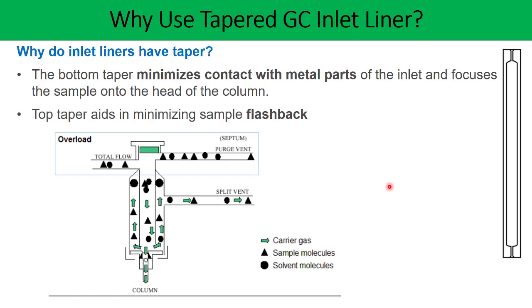The second important reason to consider using the taper liner is that the top taper aids in minimizing sample flashback. This is the top taper and this is the bottom taper. If your liner has a top taper, it minimizes flashback. Once the sample gets injected into the injector port, it undergoes vaporization and increases its volume. If your liner is not able to hold this increased volume, your sample along with the diluent can flashback, and because of this, your sample may travel through the inlet carrier gas line or towards the septum purge line — this is called flashback.